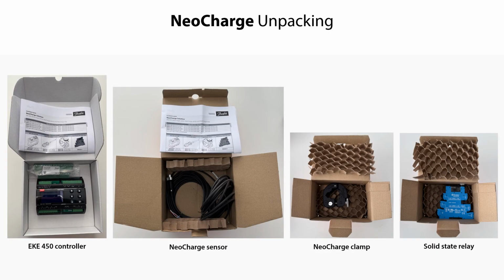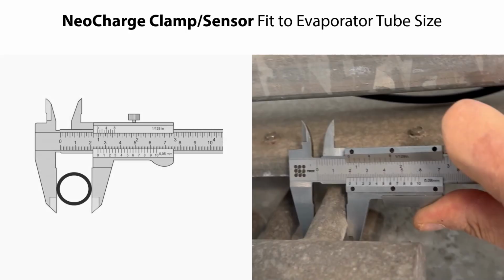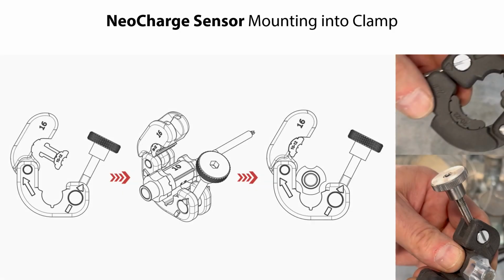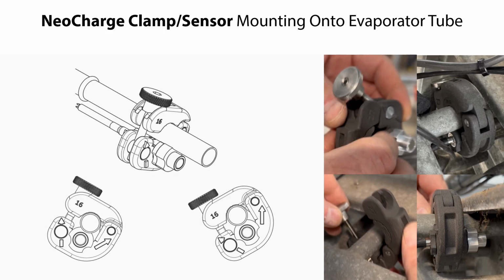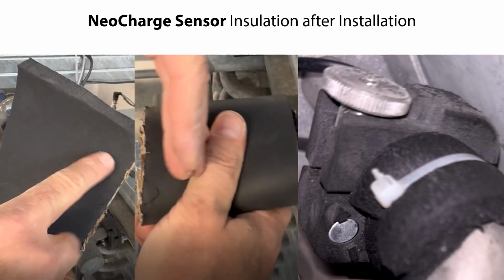What is included in the Neocharge box when unpacking it? How to ensure that the Neocharge clamp with sensor will fit to a given evaporator tube size. How to mount the Neocharge sensor into the clamp. How to locate, orient and fix the clamp with sensor onto the evaporator tube. How to insulate the Neocharge sensor after installation.